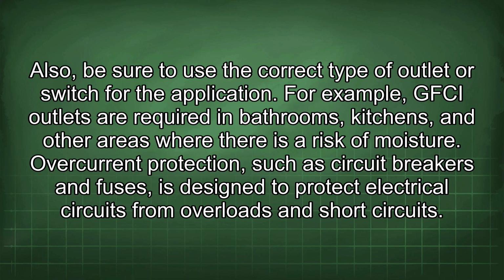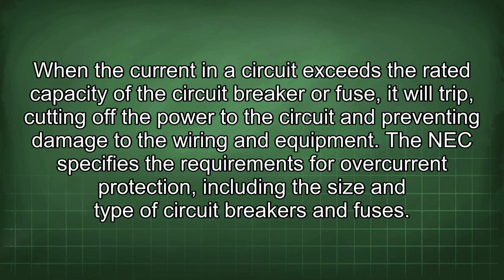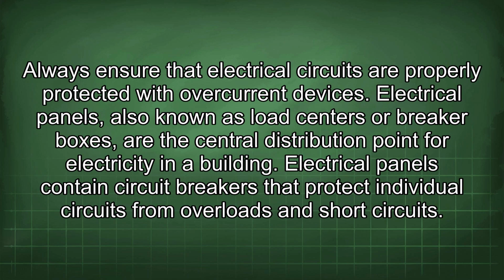Overcurrent protection, such as circuit breakers and fuses, is designed to protect electrical circuits from overloads and short circuits. When the current in a circuit exceeds the rated capacity of the circuit breaker or fuse, it will trip, cutting off the power to the circuit and preventing damage to the wiring and equipment. The NEC specifies the requirements for overcurrent protection, including the size and type of circuit breakers and fuses. Always ensure that electrical circuits are properly protected with overcurrent devices.